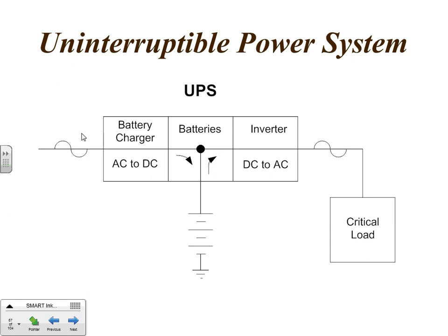So if the power fails here, we still have the connection to the battery, so the inverter is still going to work, right? So the critical load has seen nothing happen. That wave is still there. That gives us a chance over here to start our generator set, transfer power, boom, replenish this. Now this battery charger fires up and it's replenishing the power that it took to run this load while the power was off. So virtually uninterruptible.